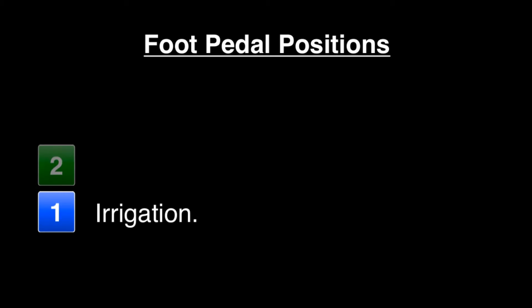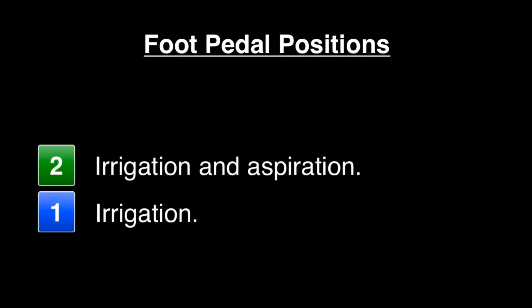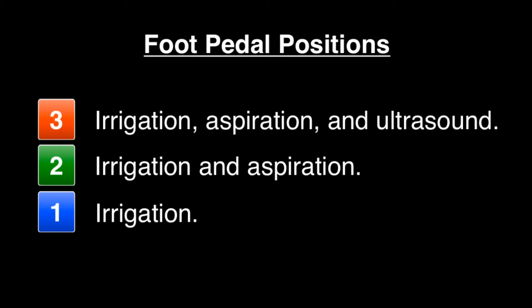Besides dynamics and settings of different phaco machines, you also need to familiarize yourself with the three positions of the phaco foot pedal. Those positions are: position 1, which is irrigation only; position 2, irrigation and aspiration; and position 3, which includes irrigation, aspiration, and ultrasound.